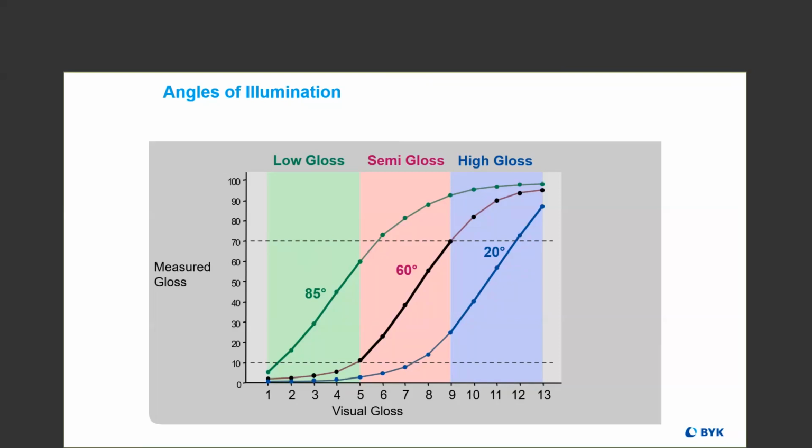Yes, I'd say so, because the BYK-mac, the multi-angle color instrument, has a directional light source, which makes the geometry similar to the 45/0, where it's going to measure color as you see it, and the gloss differences are going to have an effect on the color differences.